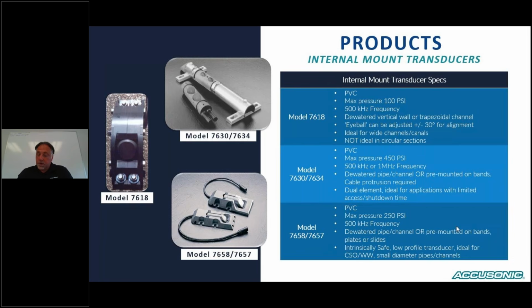And then probably our most popular internal mount transducer is the Model 7658 transducer. It's all PVC construction. These transducers are good to about 250 psi. They can be encased in concrete, or it can be in an open channel application. It's a pretty versatile transducer. It's also very low profile, so it doesn't create too much disturbance in the flow stream. One thing that I didn't mention before is our internal mount transducers operate at a frequency of 500 kilohertz, and our feed-through style transducers are 1 megahertz.